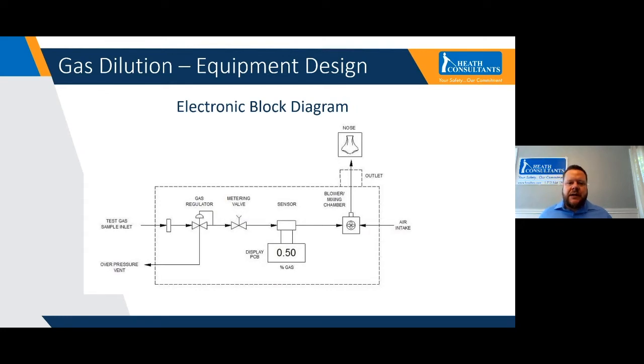Essentially, you connect this piece of equipment to your natural gas or combustible gas stream through the gas sample inlet, and it passes through a gas regulator to bring the pressure down to a safe level.